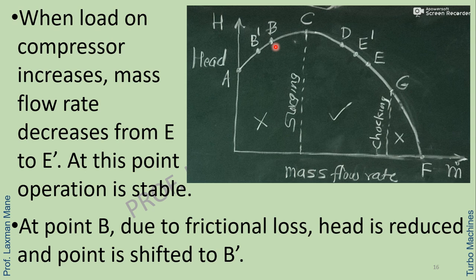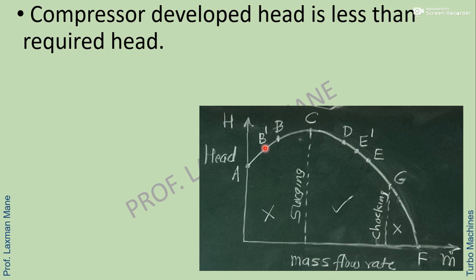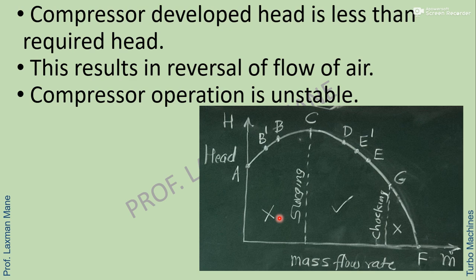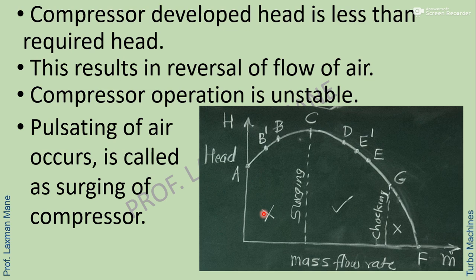At point B, due to frictional loss, if head is reduced, point B shifts to B-dash, meaning the compressor developed head is less than the required head. Compressor developed head is responsible for moving air in the delivery pipe. When developed head is less than required head, this results in reversal of air flow and unstable compressor operation. Pulsating of air occurs here, which is called surging of the compressor.